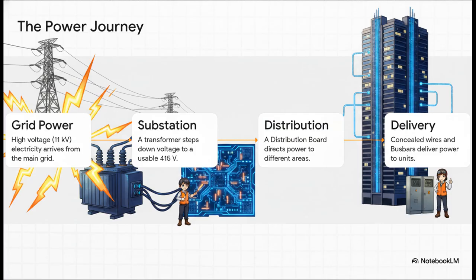So check this out. This is the entire journey. Power comes in from the main grid at a staggering 11,000 volts, way too hot to handle. So the building has its own substation that steps that voltage way down to a much safer 415 volts. From there, a distribution board acts like a traffic cop, telling the power where to go.